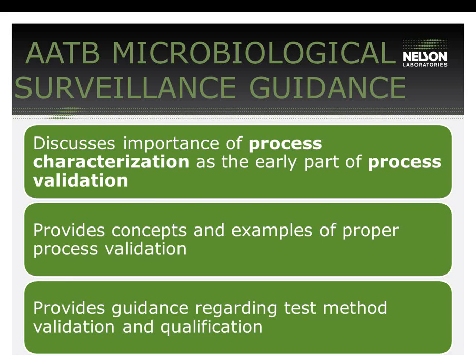So this guidance document from AATB discusses the importance of process characterization as an early part of process validation. That's something that is discussed pretty well in the FDA guidance document that I referred you to. And I think this is something that is largely overlooked in the tissue industry, where sometimes process characterization is not addressed as thoroughly as it should be before people go right into process validation.